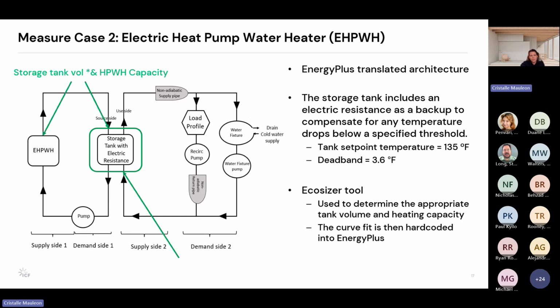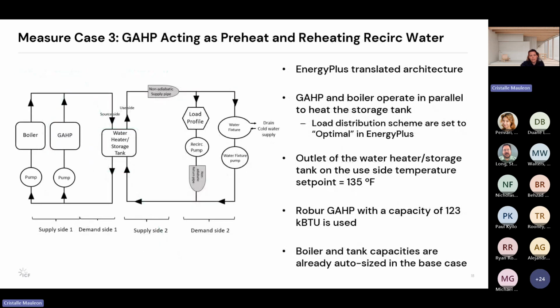And then for the GAHP, the boiler and the water heater storage tank are going to be already auto-sized from the baseline model. And we are simply adding an additional capacity of the GAHP. So in this case, we were using the 123 kBTU GAHP. And the reason that we decided to do that instead of having auto-sizing going on is because generally, in a retrofit situation, you're going to leave the boiler and the storage tank there, and you're going to add a GAHP onto the system. So we thought that that was the most realistic modeling scenario.